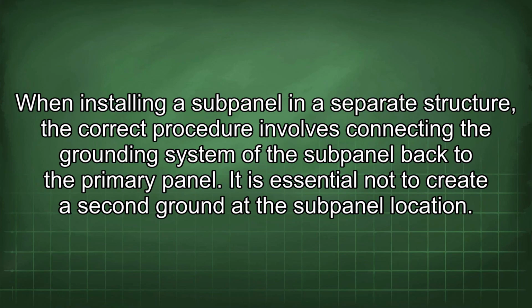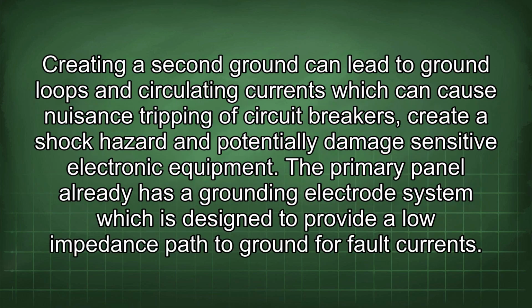When installing a subpanel in a separate structure, the correct procedure involves connecting the grounding system of the subpanel back to the primary panel. It is essential not to create a second ground at the subpanel location. Creating a second ground can lead to ground loops and circulating currents, which can cause nuisance tripping of circuit breakers, create a shock hazard, and potentially damage sensitive electronic equipment.